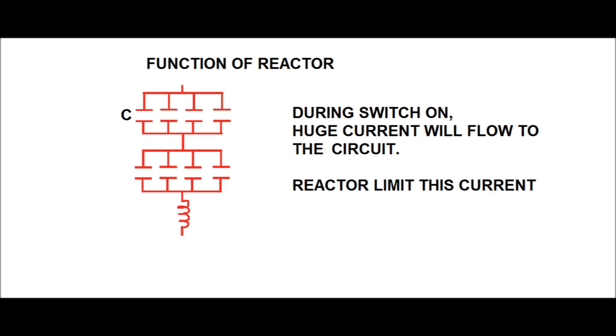Now, what is the function of the reactor connected in series in each phase of each star connection? Whenever the capacitor bank is switched on, a huge inrush current flows due to the presence of the capacitance. To limit this inrush current, a series reactor is used, connected in series with the capacitor unit in each phase of each star connection.